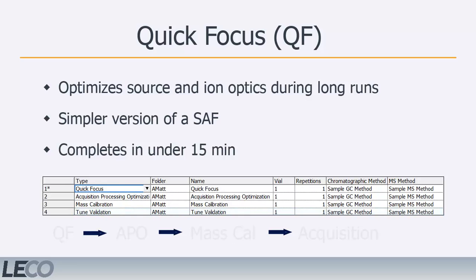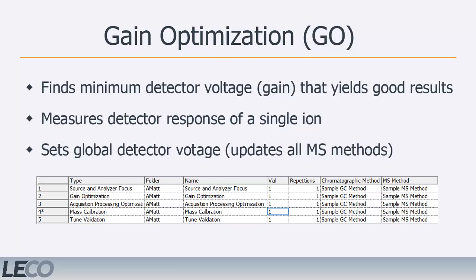A gain optimization, or GO, is designed to find the minimum detector setting that yields good isotopic ratios for low-intensity ions in order to compensate for the aging of the detector. Additionally, the gain optimization determines the detector response for a single ion. This information is critically important to the automatic data filter and compression routines. Once performed, the gain optimization sets the detector voltage globally for the instrument, automatically updating all operational mass spec methods.